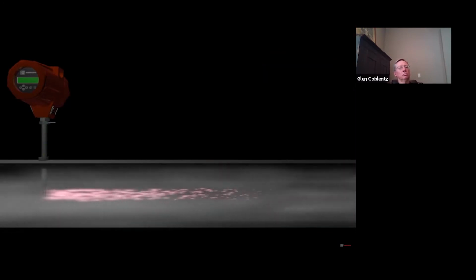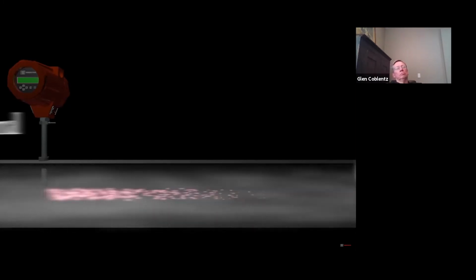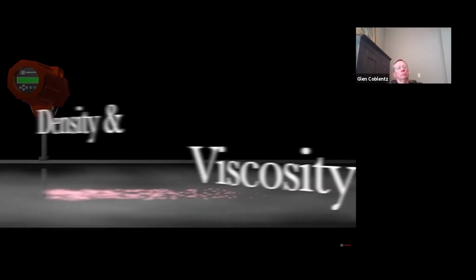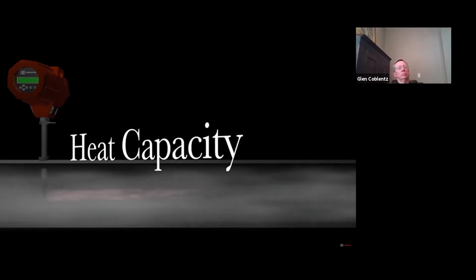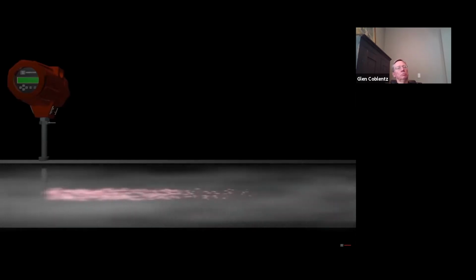It is important to note that heat transfer from flowing gas is affected by the properties of the gas. These are known gas properties like thermal conductivity, density and viscosity, and heat capacity. All of these must be understood and accounted for when a thermal meter is calibrated to assure best accuracy. For example, at the same mass flow rate, a hydrogen molecule will carry away more heat because it has higher thermal conductivity than, for instance, a nitrogen molecule. The thermal meter must account for this difference to be accurate.